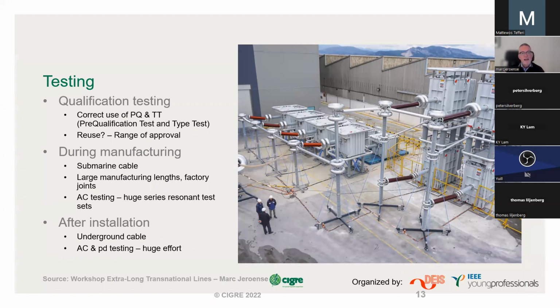That means that if we test these lengths, even for a DC cable, with AC—because AC is still seen as a better tool, a better voltage to detect failures and issues with the cable—we need huge series resonance test sets to test these many kilometers of cable. And if in future we leave the sweet spot of 525 kV and go to 600 kV or maybe even 700, who knows where it ends, the AC testing voltage would also increase. If the lengths also increase, we reach a point where the series resonance test sets become incredibly large. I won't say it's impossible, but it becomes large at least, and we have to think about whether it should continue or not.